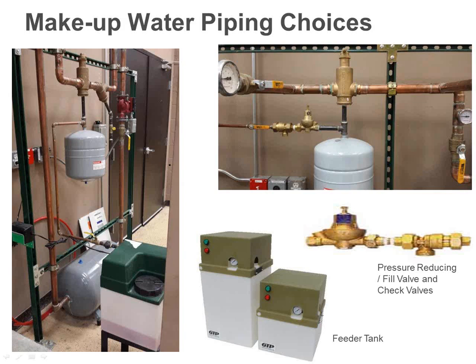Okay. Bill, we did have a question come in from Fazal. He asks, for a high-rise building, what is the ideal location of the expansion tank? In most of your high-rise buildings, your expansion tank you want to find up on the upper floors. A lot of the times in these older buildings, these 25, 30-story buildings, you're going to find the whole boiler system up in the penthouse. But most of the time, you want to have that expansion system, if you can, keep it up at the highest point of the building on a high-rise. It makes the tank smaller in size. You don't have to deal with the higher pressures that would be normally required down in the basement.